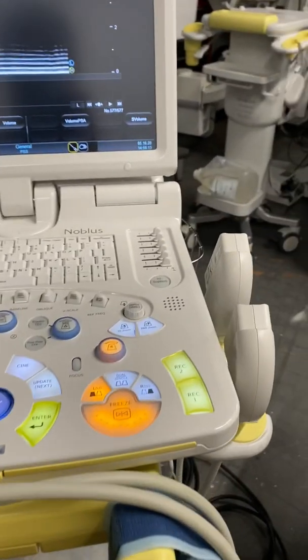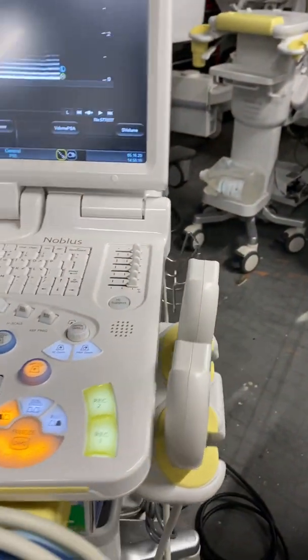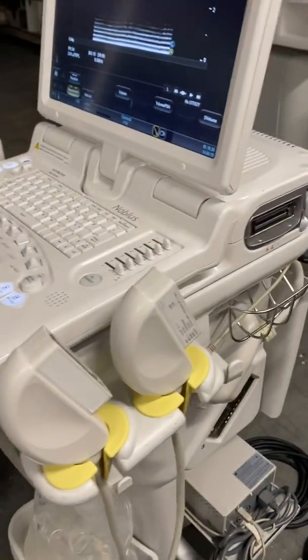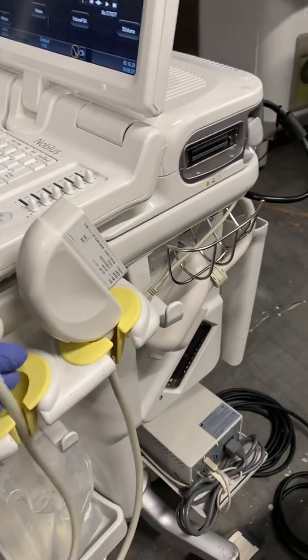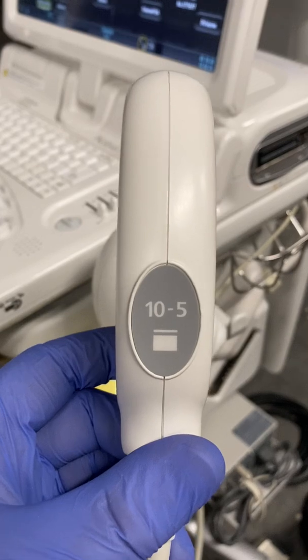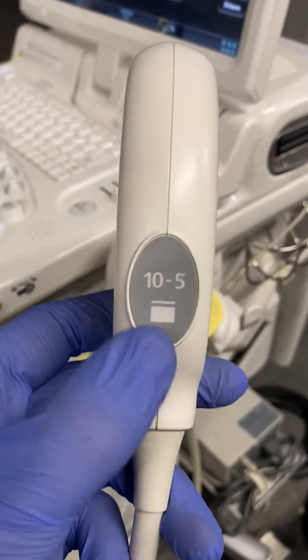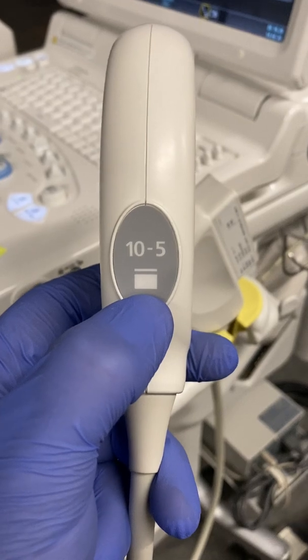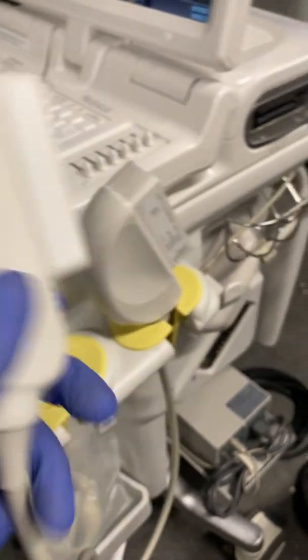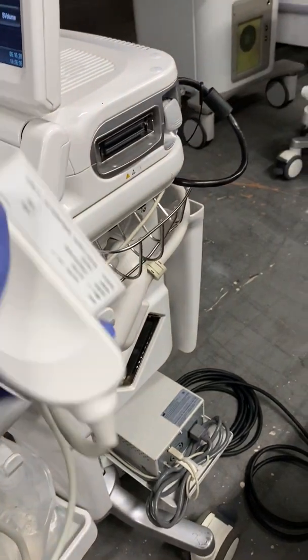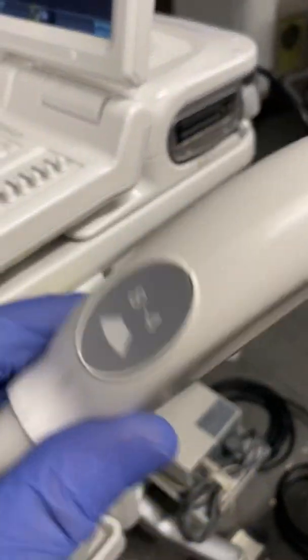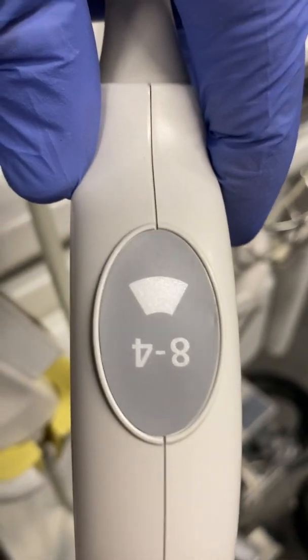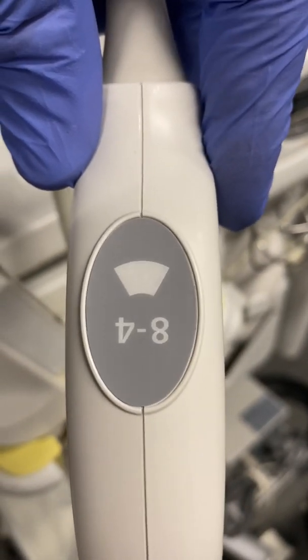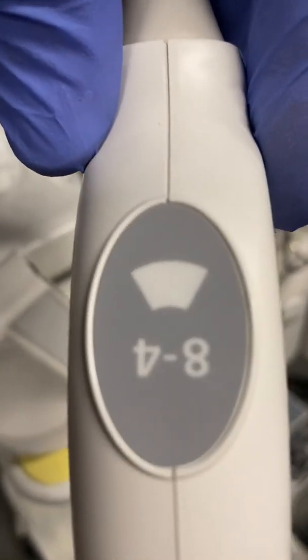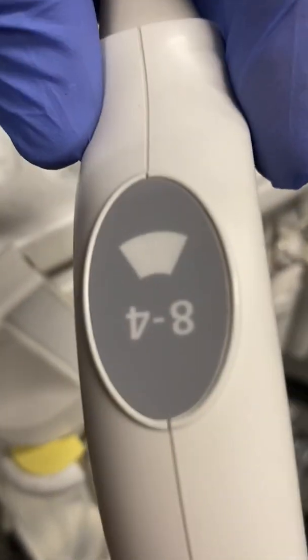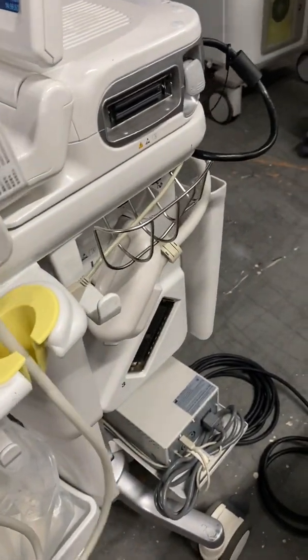So this probe here has two connectors, one for each crystal, as opposed to the C41V, which has only one connector. So obviously each crystal has its own connector, and you can tell which one it is by looking at these pictures. So this linear, kind of square shape is the sagittal connector. And then this one obviously is the axial, but you can tell because it has that fan shape. Just like how we see the gland with the C41V in axial, if you can imagine the picture, it has this kind of shape on the monitor. So this is the axial crystal connector.